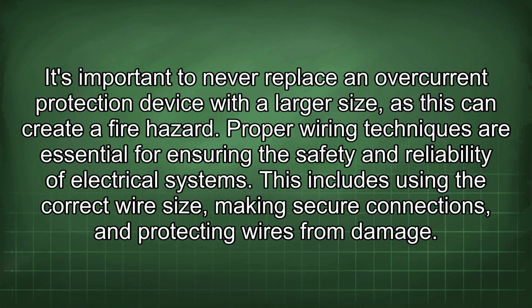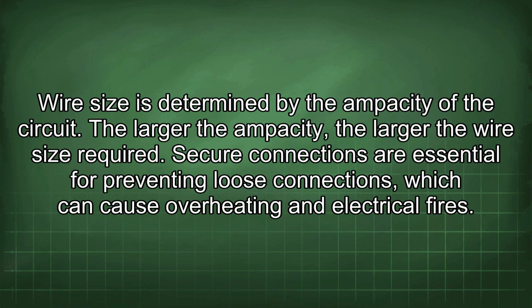It's important to never replace an overcurrent protection device with a larger size, as this can create a fire hazard. Proper wiring techniques are essential for ensuring the safety and reliability of electrical systems. This includes using the correct wire size, making secure connections, and protecting wires from damage. Wire size is determined by the ampacity of the circuit. The larger the ampacity, the larger the wire size required.